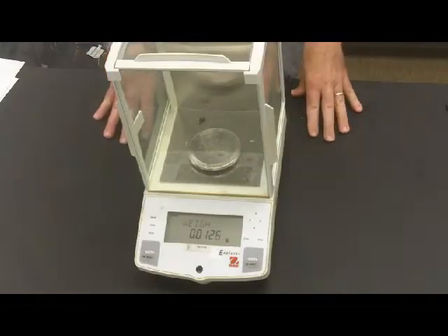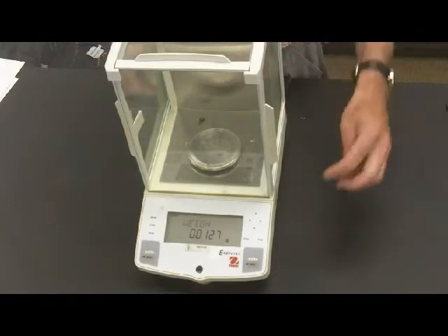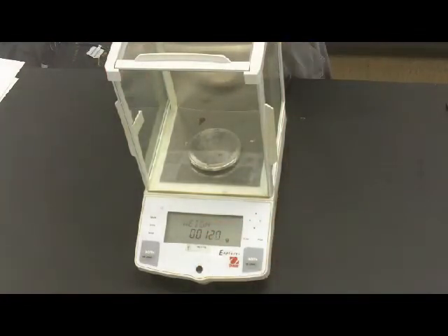Now, when you're using the analytical balance, it will look something like this. We see that it can weigh grams to the 4th decimal place. That's to the 10,000th place in grams. That is, it can distinguish weights that differ by no more than 1/10 of a milligram. We'll only use the analytical balance when we need this type of extreme sensitivity. So we will mainly use the top-loading balance.